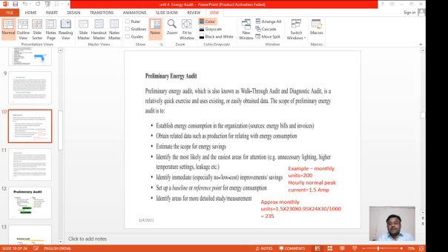Then with this data, we can compute the consumption for 1 month. Let us apply the formula that the number of units or kWh is V I cos phi. So V is 230 volt, I is 1.5, cos phi is 0.95.